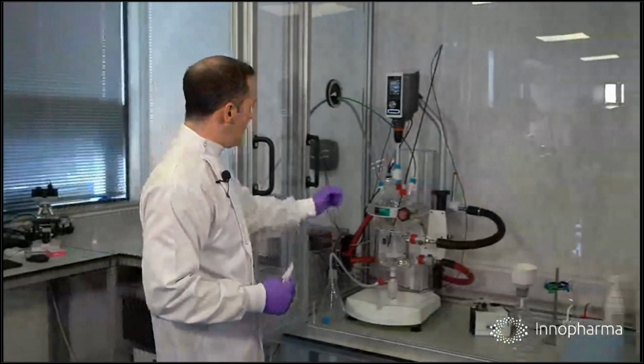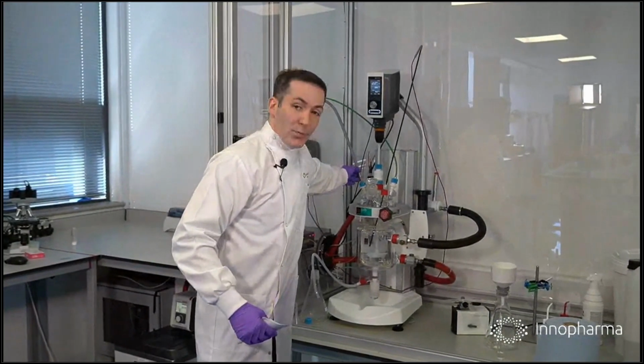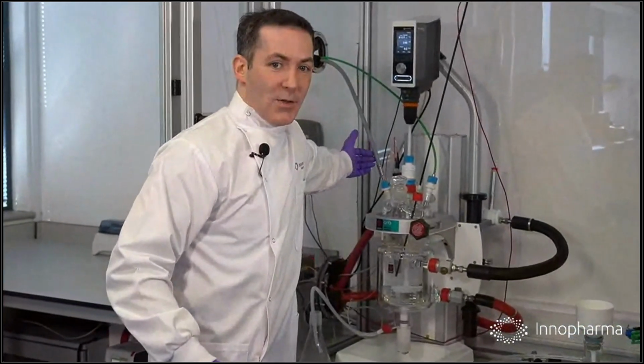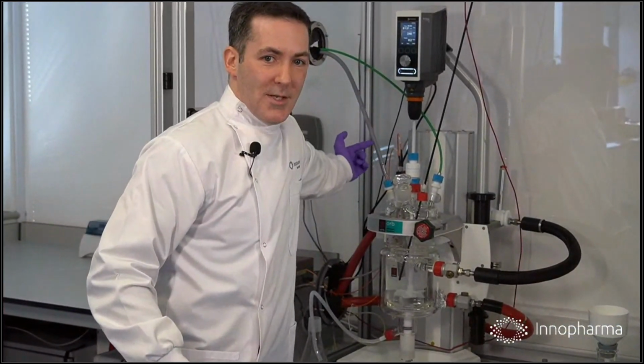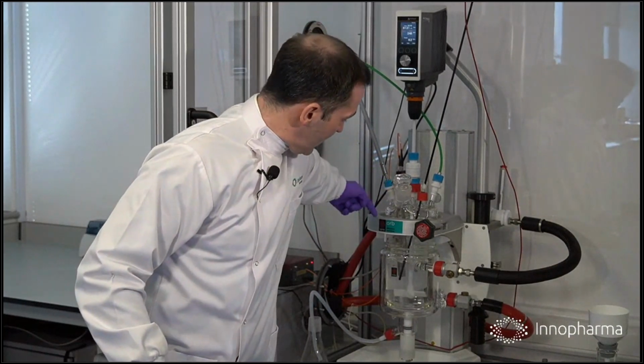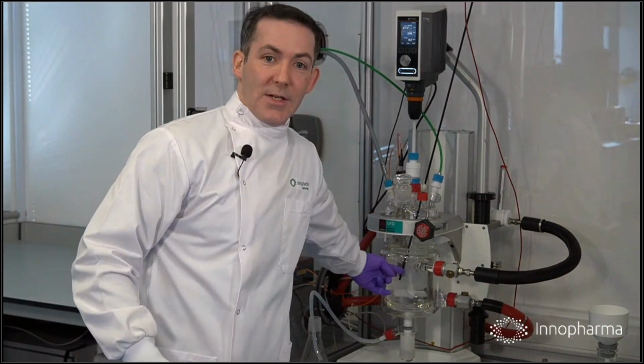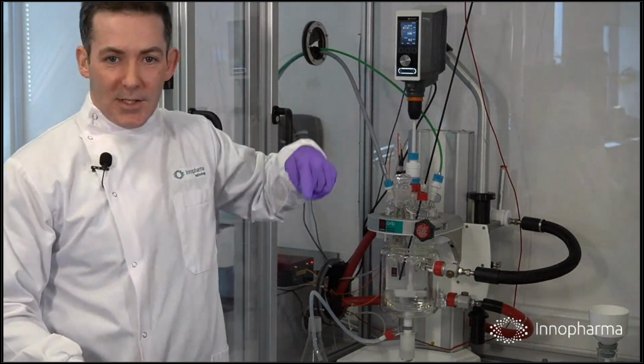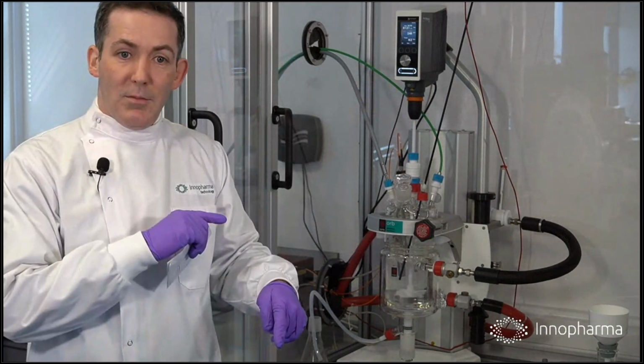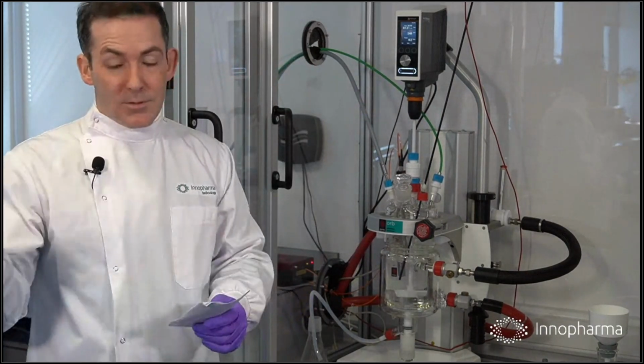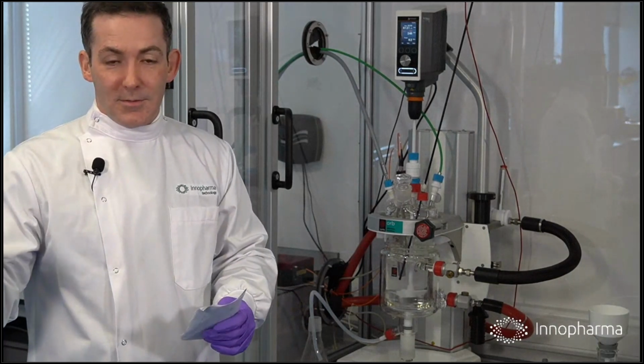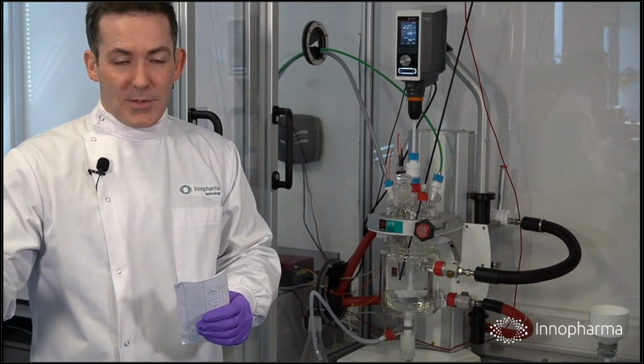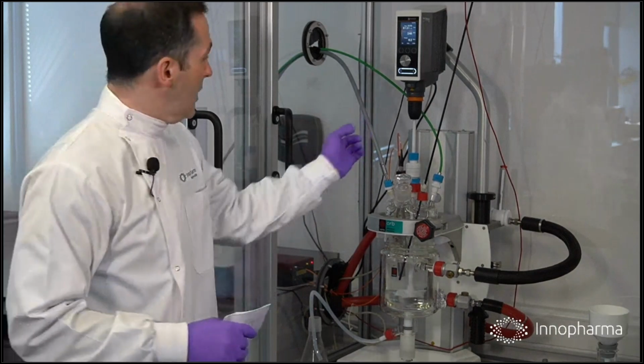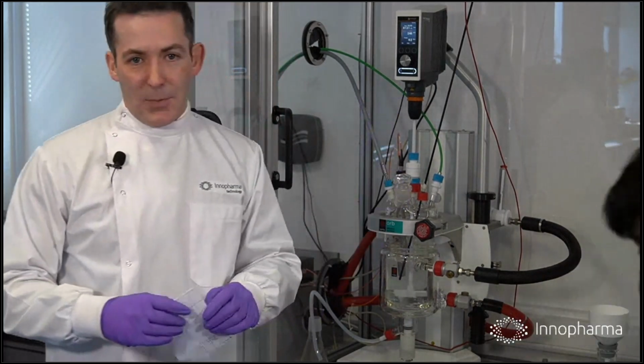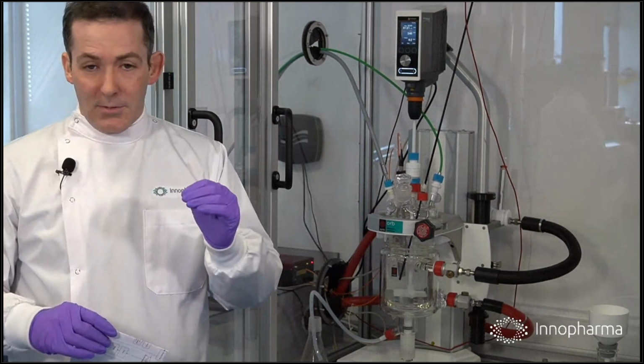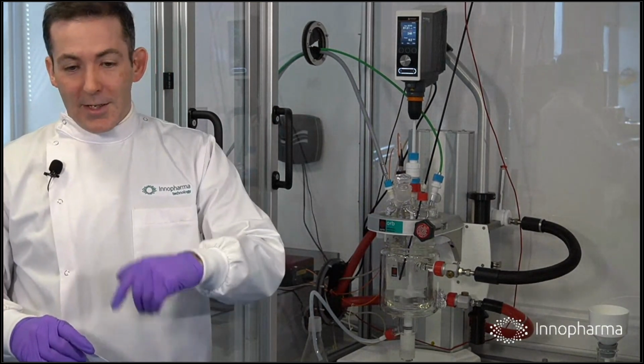So I'll show you again these probes here. This probe is seeing directly inside the process. It has fiber optic cables that are directed right into the reaction vessel itself. So light is delivered into and then collected from the solution. We'll talk about how that's converted so we get actual light signals from the solution as well. But similarly, with our Raman spectroscopy instrument, laser light is being delivered to the solution and collected.